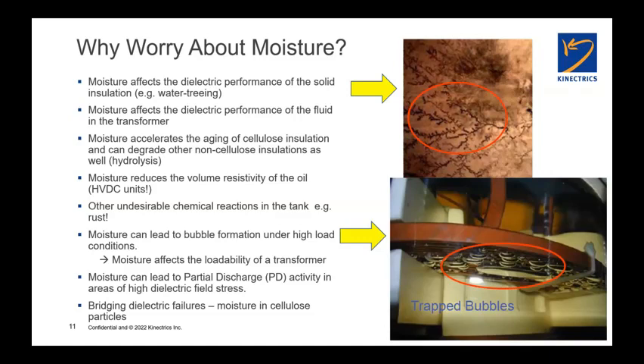Moisture in HVDC transformers, which are a real special breed of unit used on obviously HVDC transmission systems, affects the volume resistivity of the oil and the paper in the transformer. When we design conventional transformers, the insulation design is done on the basis of alternating current capacitances and the relative permittivities of the insulation materials. On DC units, we're more concerned about the volume resistivity of the insulation materials used. And again, moisture has a big effect on that.